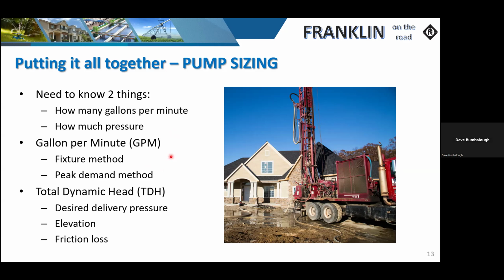Once we have the gallons per minute, we're going to move on to TDH, total dynamic head, which includes three factors. The first one is, what kind of delivery pressure do we need for the application? What are the elevation changes? Where is that water being brought from, and where is it going to be delivered to? And then we're getting it there through a piece of pipe in most cases. So we have to figure out friction loss, which includes many different factors. Friction loss could come in the form of basically tees, 90s, the size of the pipe, and we'll go over some of that in the next few slides. But we have to take that into consideration. That can add up to basically increasing the horsepower to overcome that friction loss.